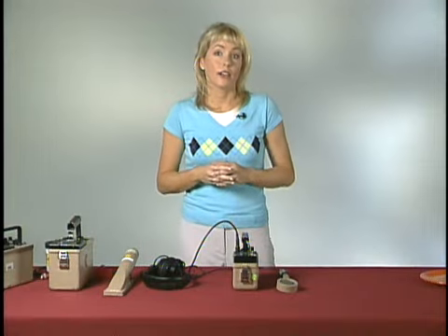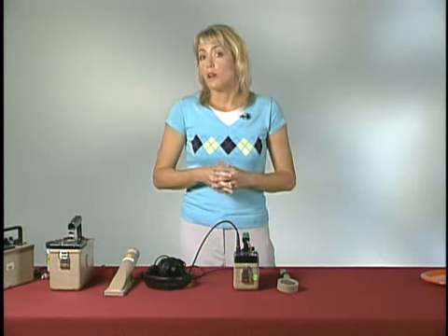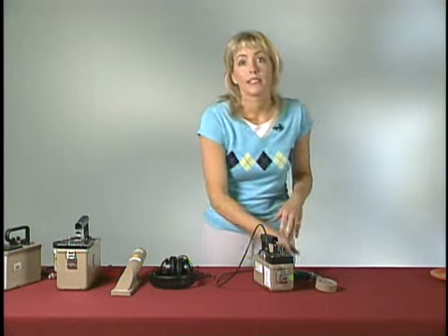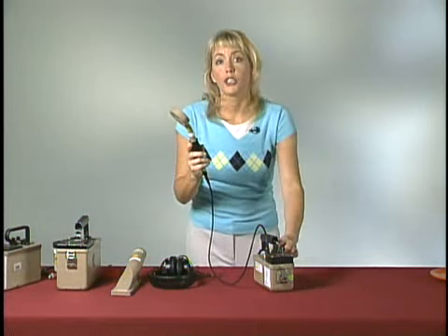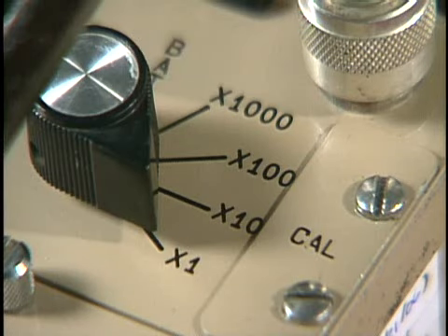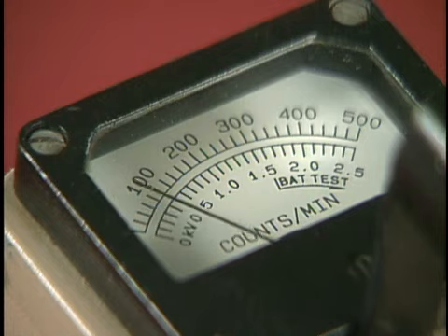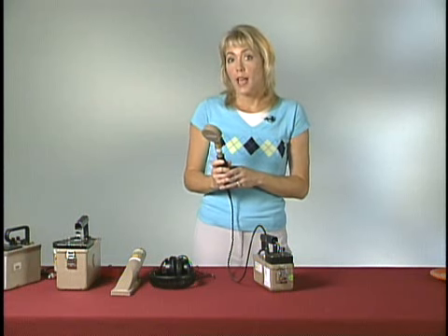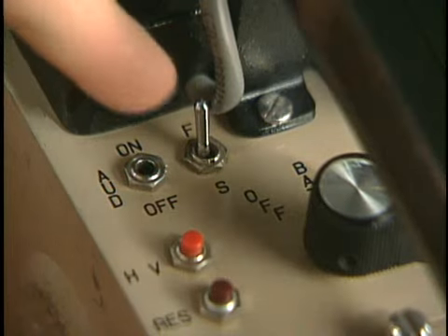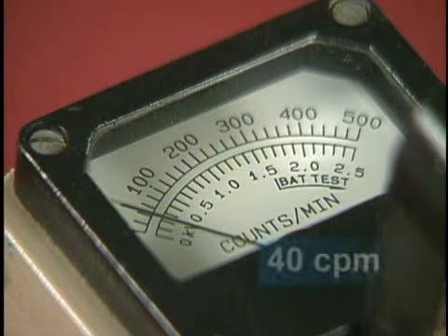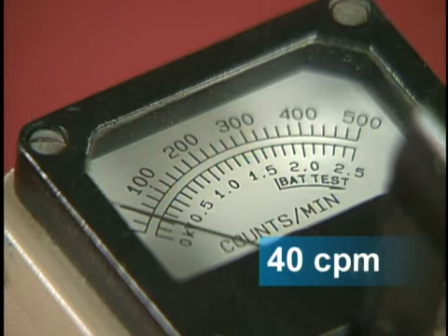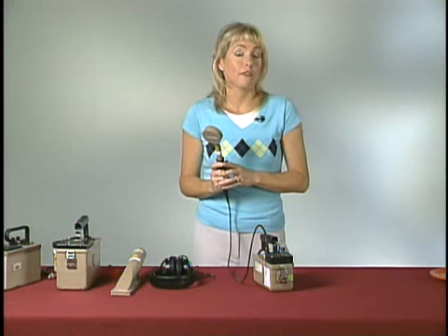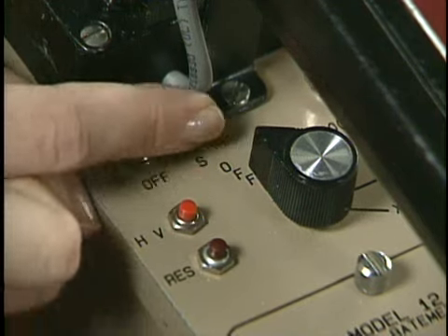One of the first things to consider, this isn't a requirement but a suggestion, is wrapping the pancake probe with a protective covering. This will prevent contamination of the detector. You can use a rubber glove or a plastic bag or saran wrap, for example. Next, I'm going to take a background reading. Make sure your range switch is set to times 1. Note that the needle fluctuates at low readings, and this is normal. You can change the toggle switch to S or slow response to make a more accurate reading. I have determined that the background count rate is 40 counts per minute, or CPM. Now make sure you move the toggle switch back to F or fast response when surveying for contamination.